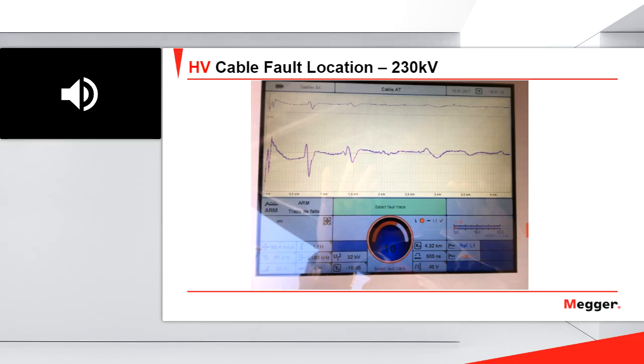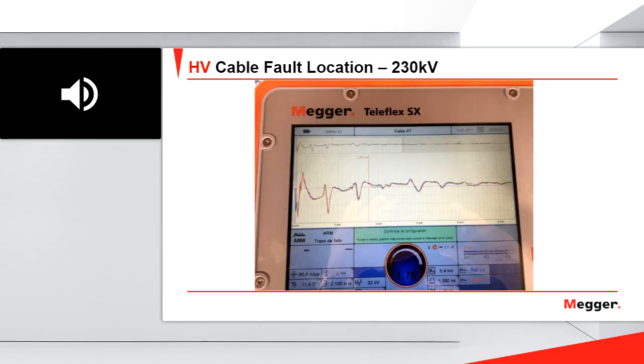As I said, we have 4 splices. You can see here 1, 2, 3. This is the 4th splice, and here is the end of the cable. This is the low voltage trace. Then we send the high voltage trace. I don't remember very well, but I think I sent a high voltage pulse of 12 kV. And then here you can see the high voltage trace.